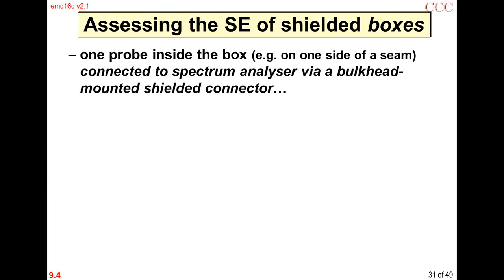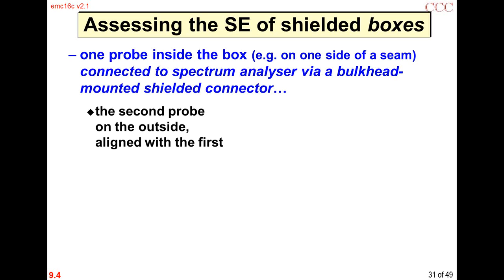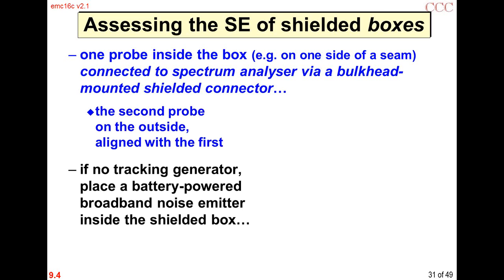Connected to the spectrum analyzer via a bulkhead mounted shielded connector, with the bulkhead mounted in the wall of the shielded box. So we're emitting the tracking generator into the enclosure, and then we have the second probe outside, aligned with the first, for measuring the shielding effectiveness of that particular part of the shield wall. If you move the probe around, you can have a look at the leakages from seams and joints and all that sort of thing.